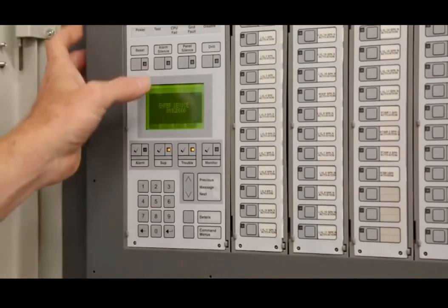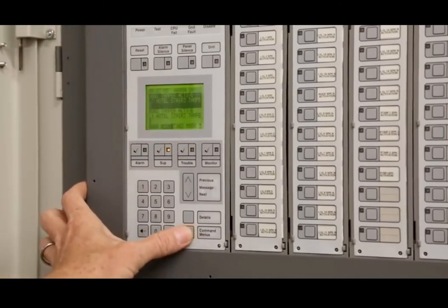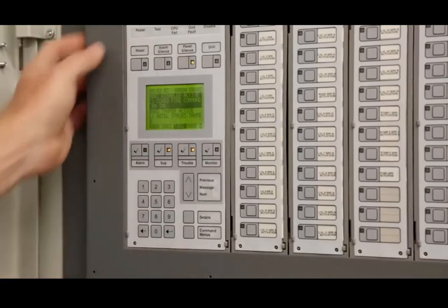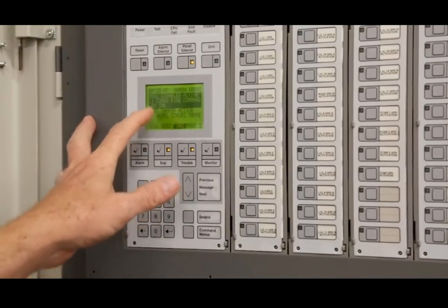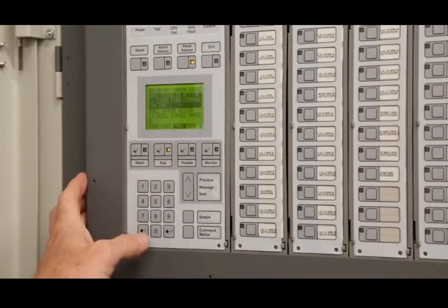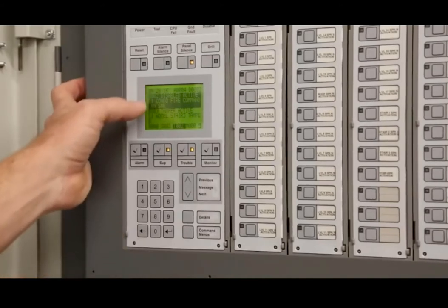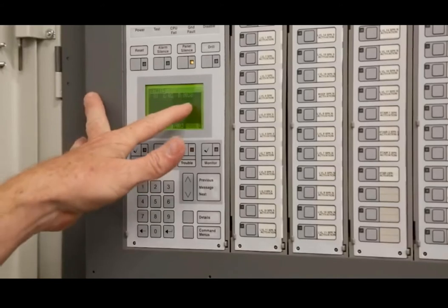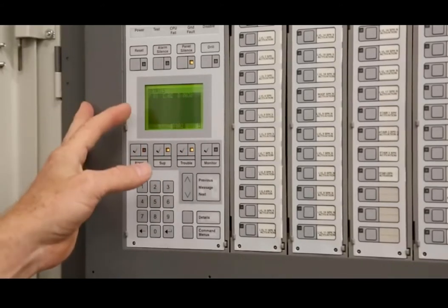Right now, if you notice the trouble came up, you can just hit the command menu to get back to it. Hit your troubles. You can silence it. Right now it just says that level 1 condo fire command room smoke is disabled. Okay. If you come in later on and you go, who disabled this device? What number is it? Whatever you're scrolling on right there, just hit details and it'll actually pull up the device number on there.